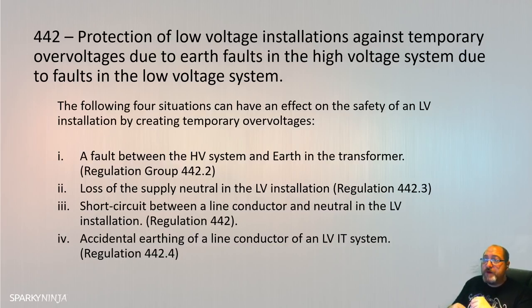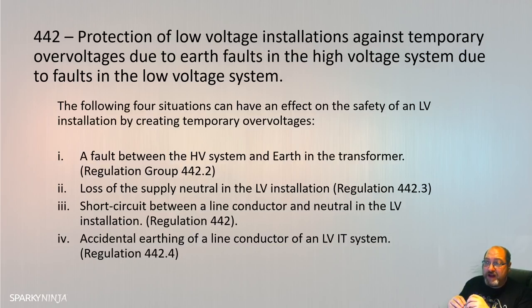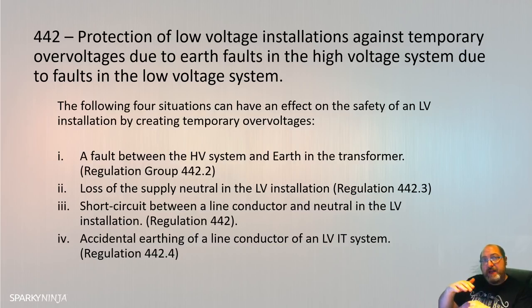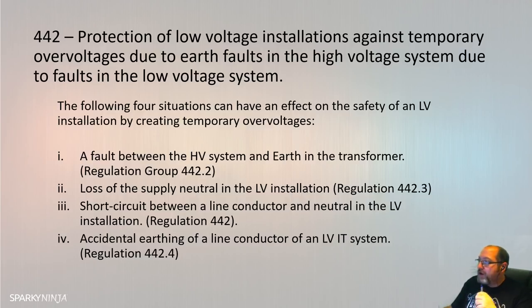The following four situations can have an effect on the safety of the low voltage system by creating temporary overvoltages. It could be a fault between the high voltage system and earth within the transformer; it could be a loss of the supply neutral in the LV system — I've seen that happen a few times. There's also a fault between the line conductor and neutral in the LV installation, and in IT systems with their deliberate high impedance between earth and the rest of the system, shorting that out will incur high voltages.